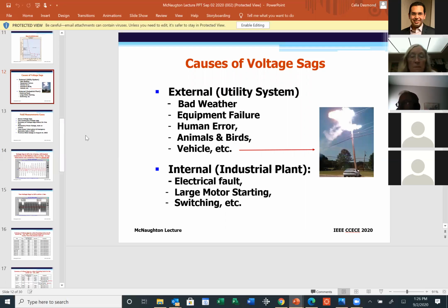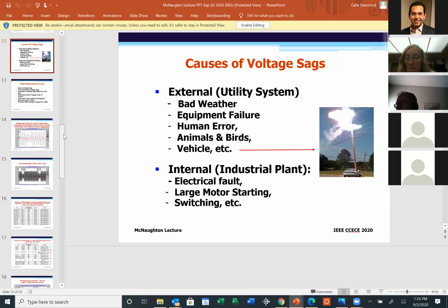If you remember in one of my slides, I said this is something we have to live with. These are the causes of voltage sags. You can see bad weather. I'm afraid we cannot do much about bad weather, meaning thunderstorms and high wind. Most of our transmission lines, if not all, are overhead, so they're very susceptible to snow, ice, and wind. When these lines get impacted and touch each other, they cause what we call a fault. And that fault, before the utility protection is activated, which as I said is typically a 100 millisecond window, causes a voltage drop. That's the sag it causes. So it's something that's out there.